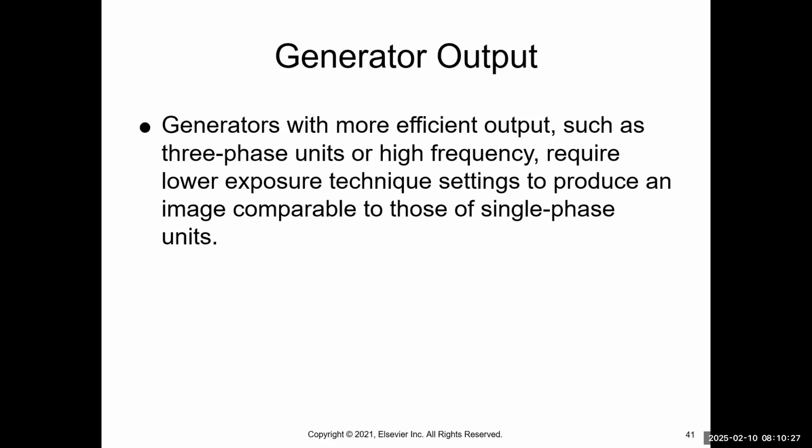When we talk about the equipment, we're talking about the generators of the equipment. So generators with more efficient output, such as 3-phase units or high frequency, require lower exposure technique settings to produce an image comparable to those of a single phase unit. So what that's saying is, very rarely are you guys going to work with single phase equipment anymore.